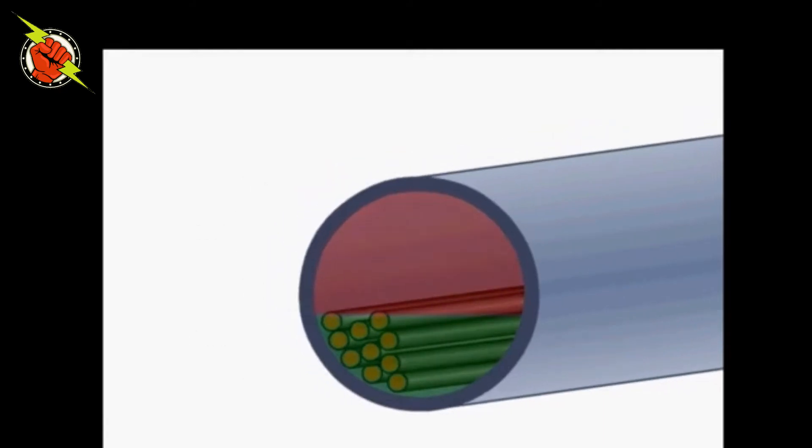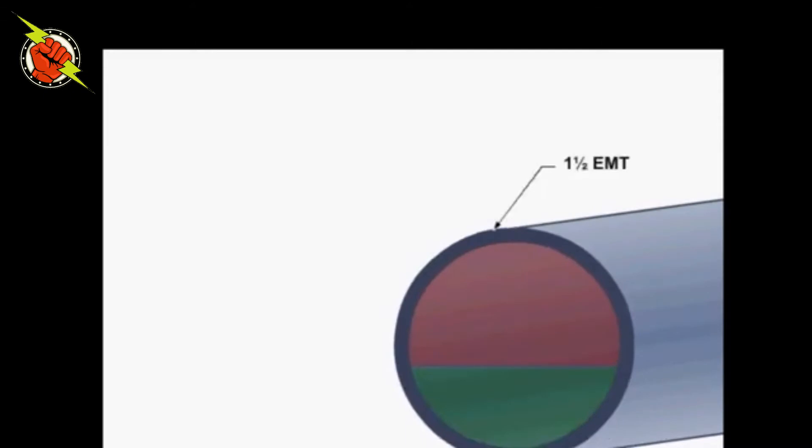If the conduit being used is 1.5-inch EMT, per Table 4 in the NEC, 40% of the cross-sectional area of 1.5-inch EMT containing more than two conductors equals 0.814 square inches.